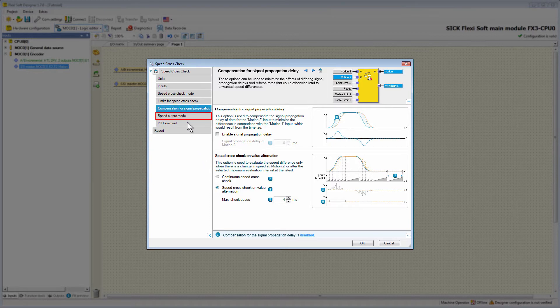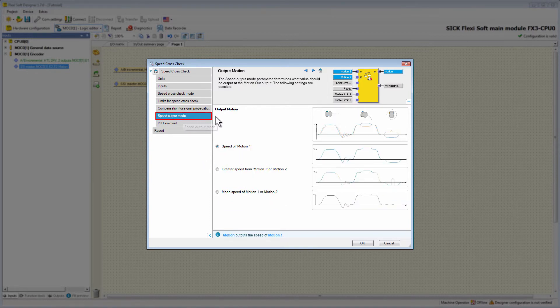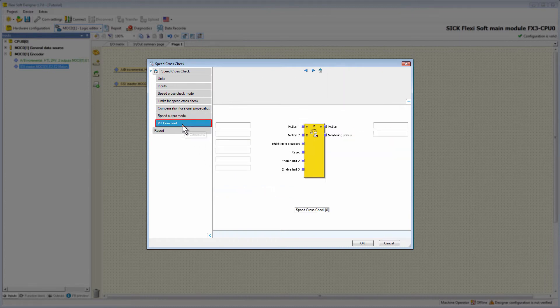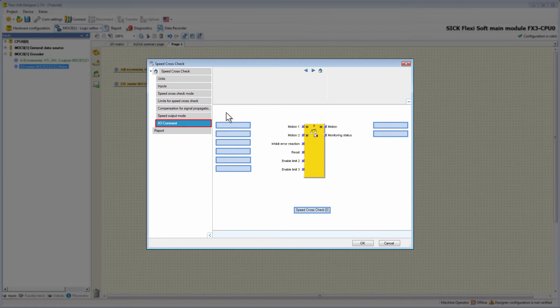Next, we switch to the tab Speed Output Mode. Here it's possible to determine what value should be output at the motion output. You can choose between the values: speed of Motion 1, greater speed from Motion 1 or Motion 2, and mean speed of Motion 1 or Motion 2. After that there is the tab I/O Comment, where we can simply give the function block as well as every input and output a new name which then appears in the logic.